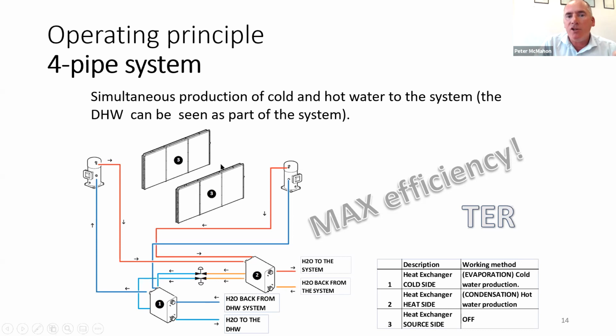So in this situation, you can see the external heat exchanger is completely out of the loop, not being used. We're pumping our refrigerant from the compressors down through the recuperator, thereby heating the water with the hot gas. Subcooled gas comes down through the expansion valve into the evaporator, cools the water because you have low pressure, low temperature gas, and then the vapor back to the compressors. So in this mode of operation, you have a new term, TER, total efficiency ratio. But again, it's the exact same, what you get out versus what you put in.